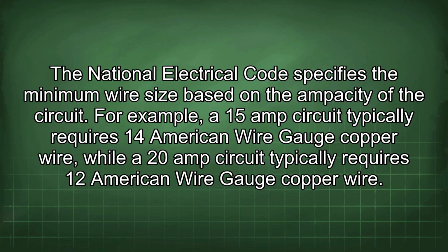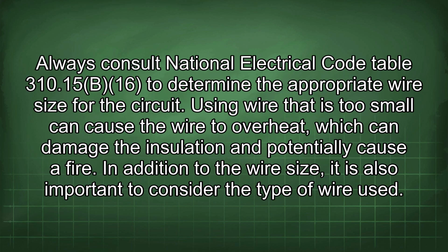For example, a 15 amp circuit typically requires 14 American wire gauge copper wire, while a 20 amp circuit typically requires 12 American wire gauge copper wire. Always consult National Electrical Code Table 310.15(B)(16) to determine the appropriate wire size for the circuit. Using wire that is too small can cause the wire to overheat, which can damage the insulation and potentially cause a fire. In addition to the wire size, it is also important to consider the type of wire used.